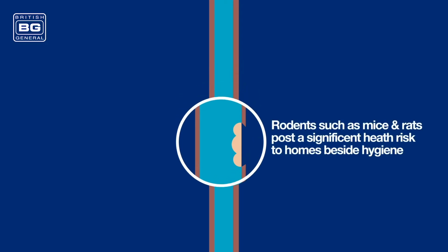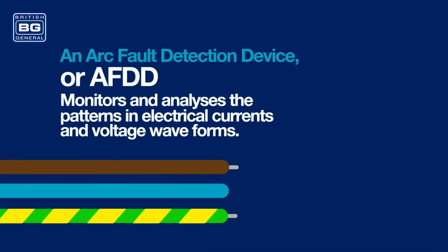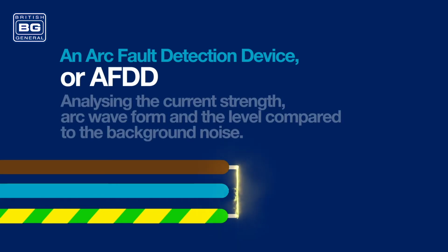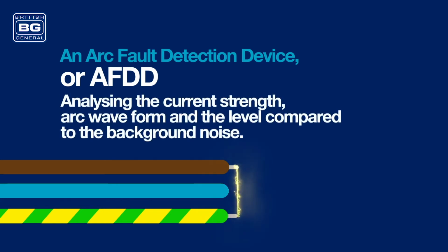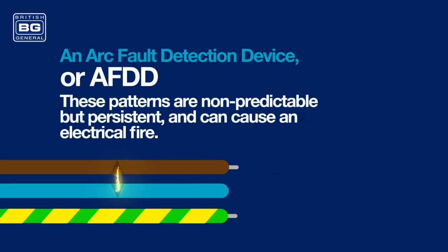This is how rodents such as mice and rats pose a significant health risk to homes besides hygiene. Another common cause of arcing is loose terminals or the deterioration of installations. An arc fault detection device, or AFDD, monitors and analyzes the patterns in electrical currents and voltage waveforms. Analyzing the current strength, arc waveform and the level compared to the background noise. These patterns are non-predictable but persistent and can cause an electrical fire. When the device detects all of these parameters in an unusual pattern, it trips and isolates the circuit.